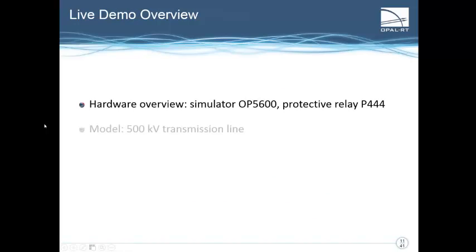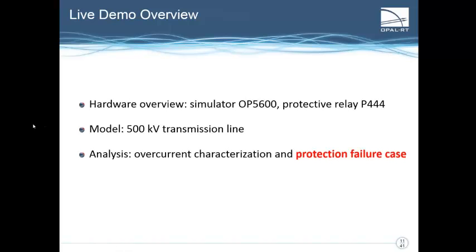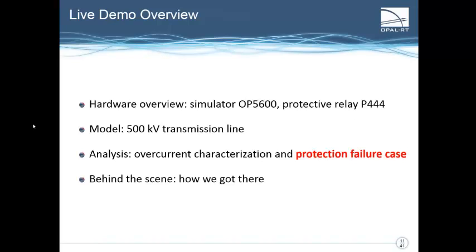First, I will quickly show an overview of the hardware we're going to use before describing the 500 kV transmission line model that helped us characterize the overcurrent behavior of the relay. Our tests made us find out that there are some cases for which the relay did not behave as expected. I'll start sharing a camera so you can see the test set. Down there we have the OP5600 on which we run HyperSim that is used for the simulation. This has 12 cores running at a frequency of 3.3 gigahertz.